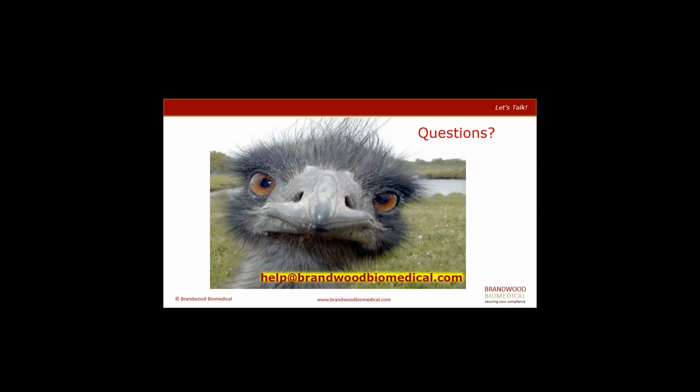So in many ways where humans are involved in the process, then that particular area within the process cannot be validated, but it's your level of confidence that's growing in the verification activities. And what you may be able to identify is, depending on what is being verified each time, if the results are consistent, then the level of verification may be able to be reduced. But no amount of verification generally identifies that the process has been validated.